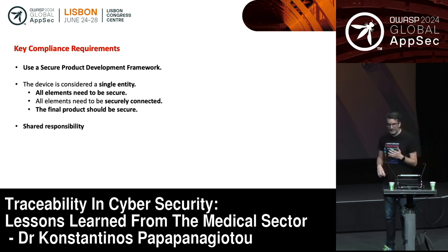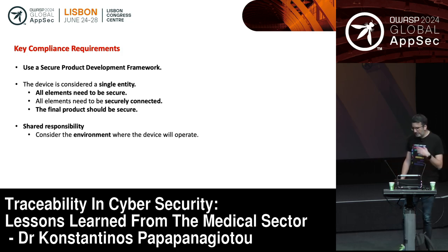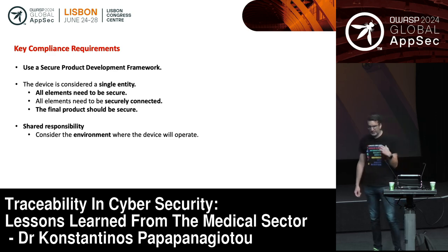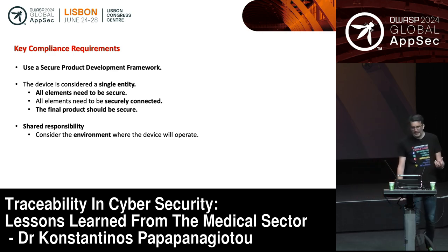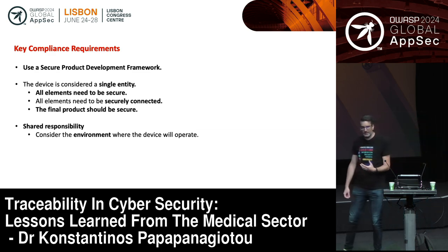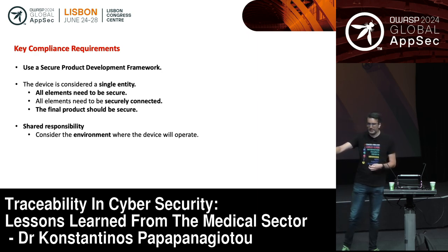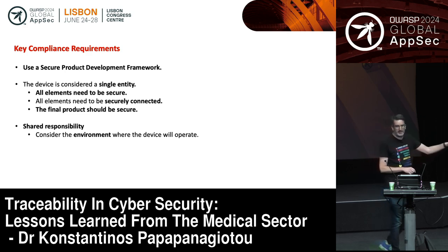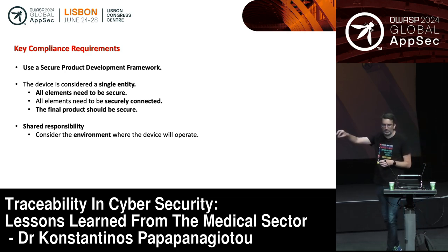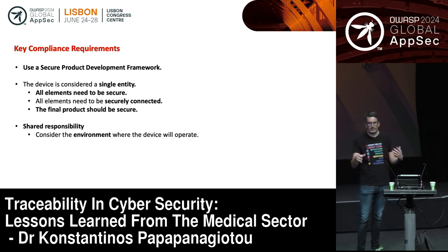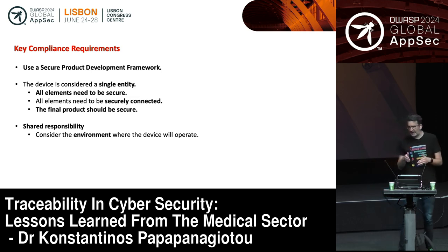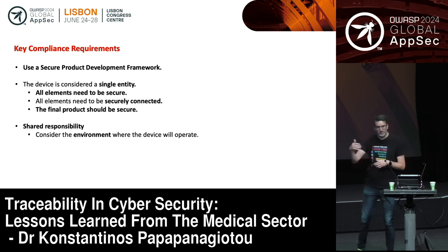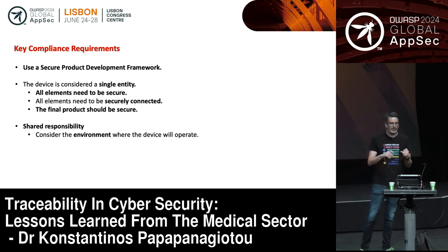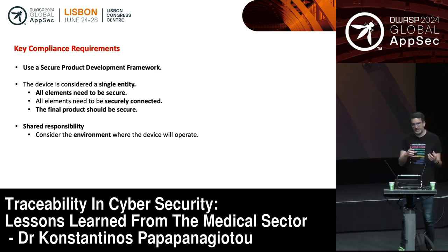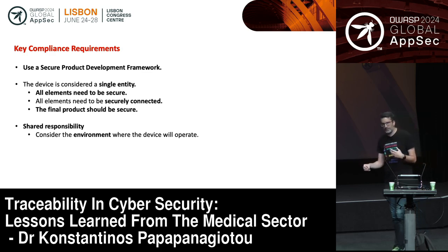Another important requirement is shared responsibility. When you build a medical device, you need to consider the environment where it will operate. You can't just tell the hospital that buys the device, 'connect it to your local network and deal with the security yourself, I don't care if someone from your network hacks it and takes control.' No, it doesn't work that way. You need to provide instructions to the buyer, the hospital IT staff, about firewalling requirements, the risks of connecting the device to the hospital network, and what they need to do to ensure it's installed and set up securely.